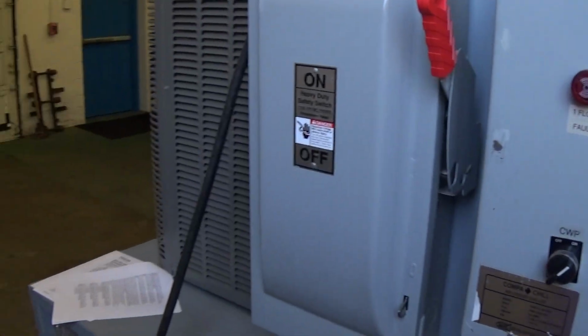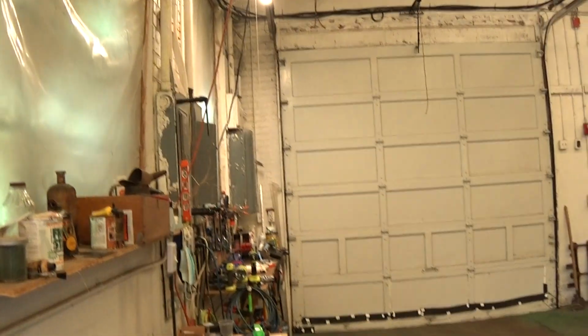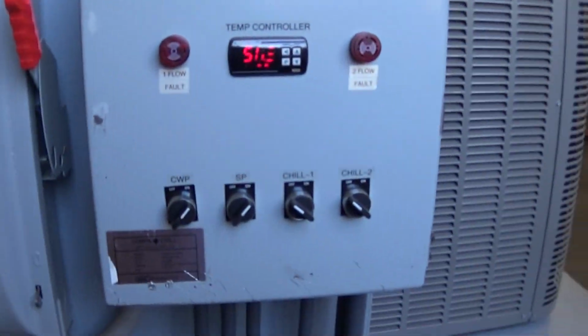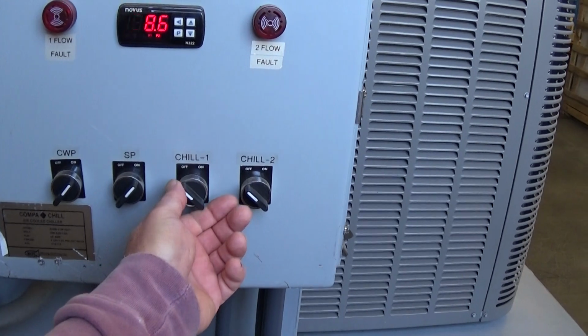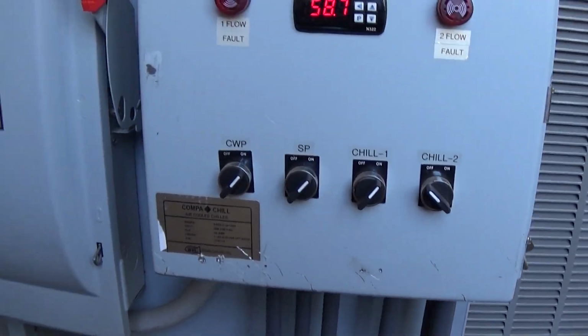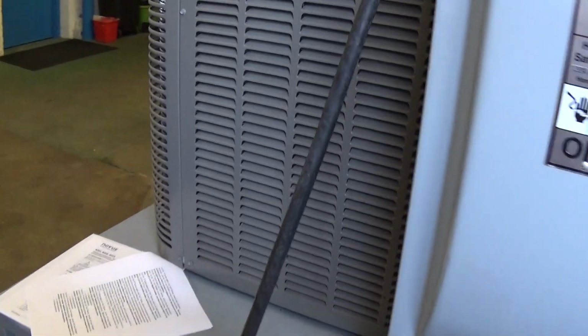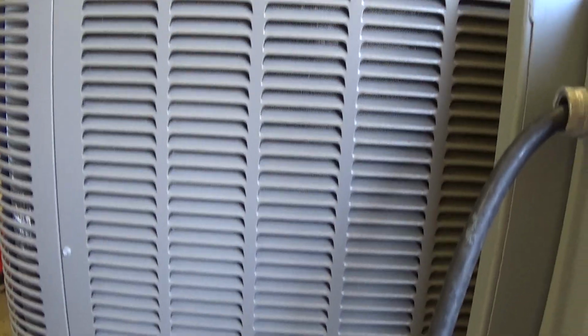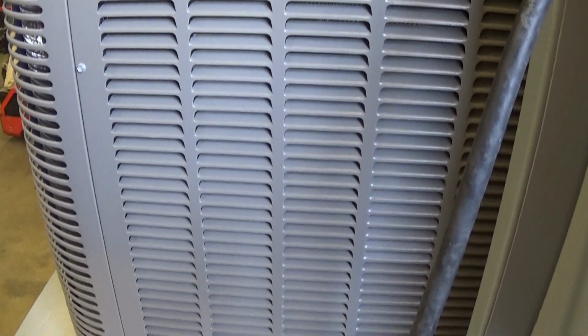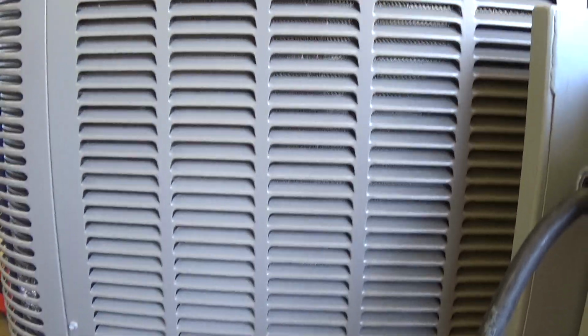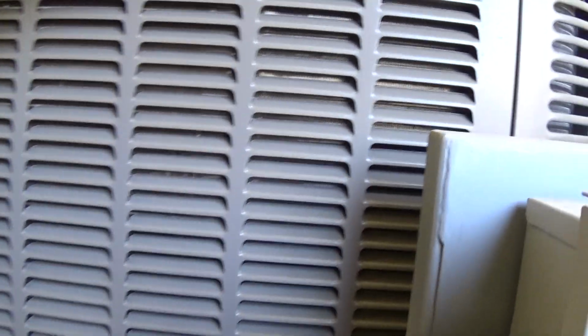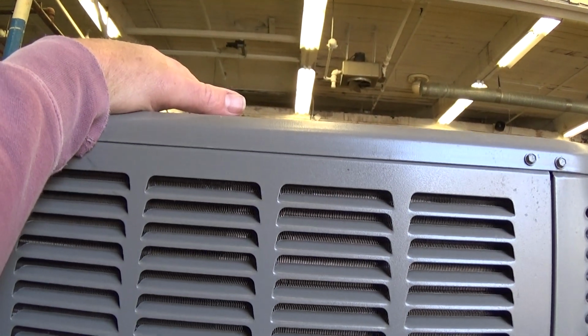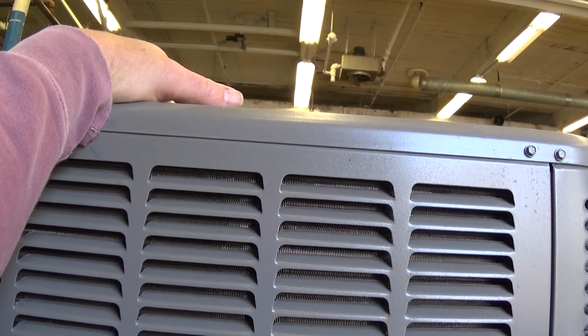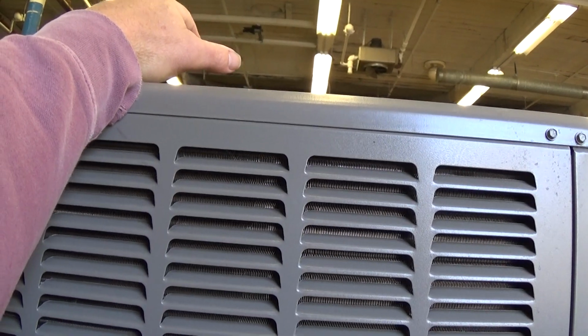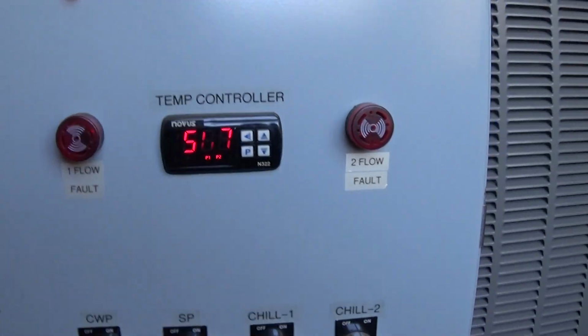We might have a limit. I don't know if we got 60 amps on our box here, but I'm going to turn on circuit 1. Pretty damn quiet, by the way. So this compressor is already running. Then as the refrigerant pressures build up, that's when the condenser fan's going to kick on. It's not on right now, but it'll probably be in 5 seconds or so. Yep. And so right now that's blowing hot air. So right now we're chilling.